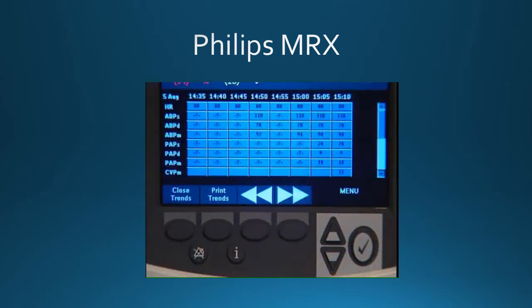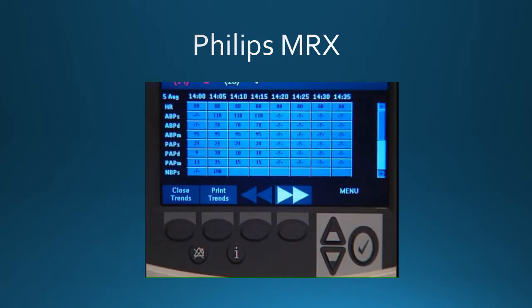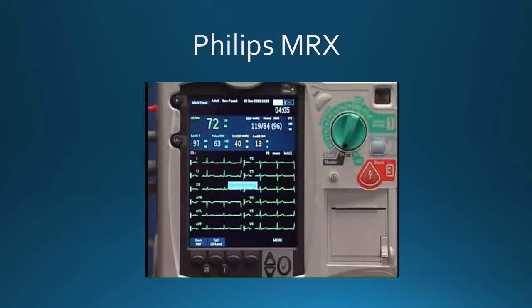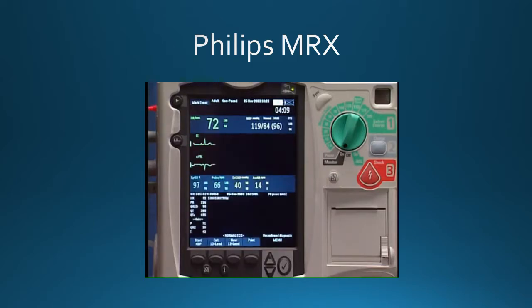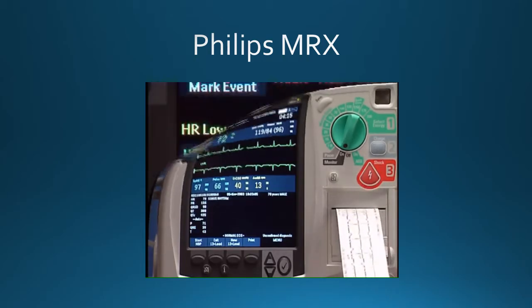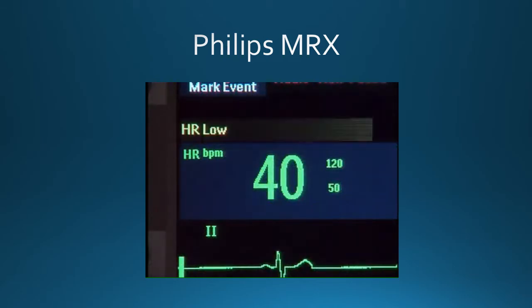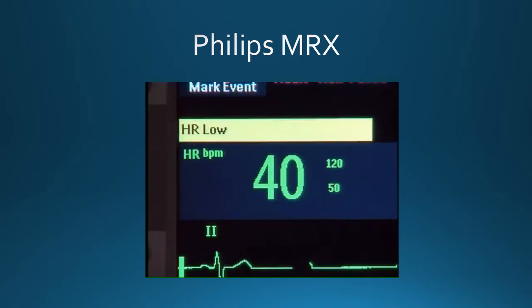The HeartStart MRX stores up to 12 hours of monitored trending data that can be displayed in time intervals on the screen. In addition, monitor mode provides an optional diagnostic 12-lead function, enabling you to acquire, store, and print 12-lead ECG reports. While monitoring, alarms alert you to changes in the patient's condition.